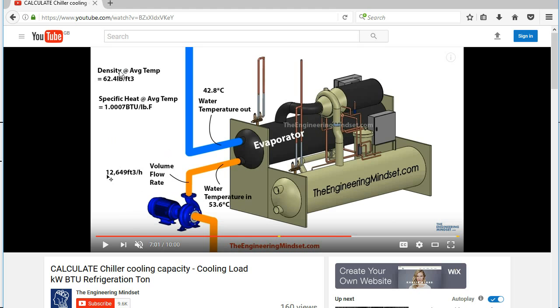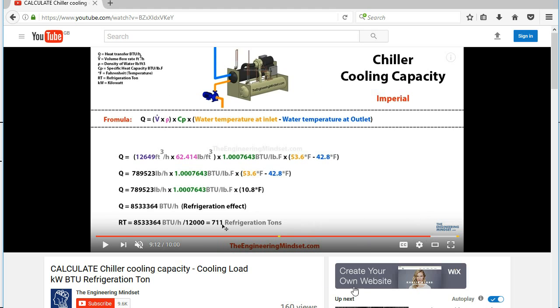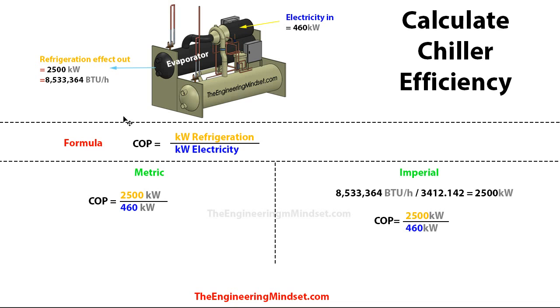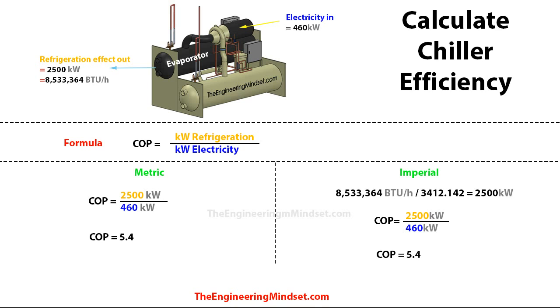I'll also explain what we need and how we get the calculations, and we'll run these through in imperial as well. So for the metric side, it's very easy — we're just going to drop in the number for the refrigeration effect out at the top of the division, and then put the amount of electricity going into the machine at the bottom. On the imperial side, first of all we want to convert from BTUs per hour into kilowatts. You just divide your BTUs per hour by 3412.142, and you'll see it comes out exactly the same as 2,500 kilowatts. Then simply do the division and you'll see that the COP comes out at 5.4.